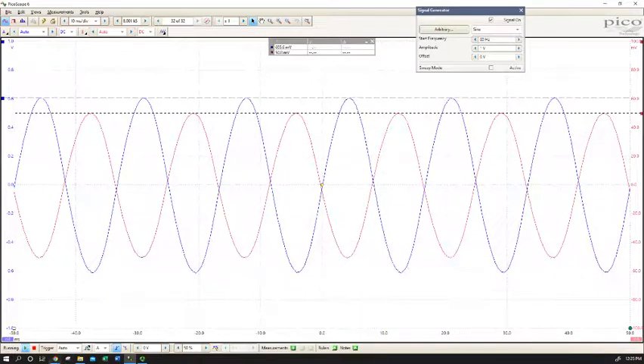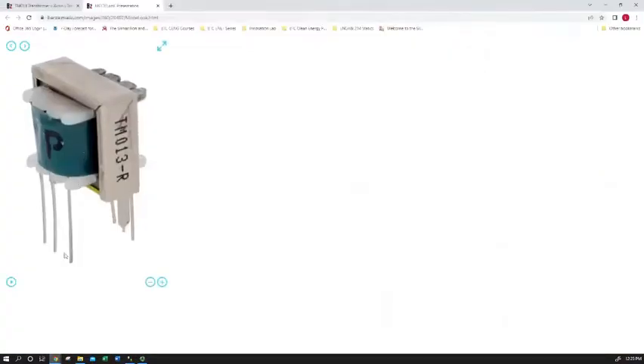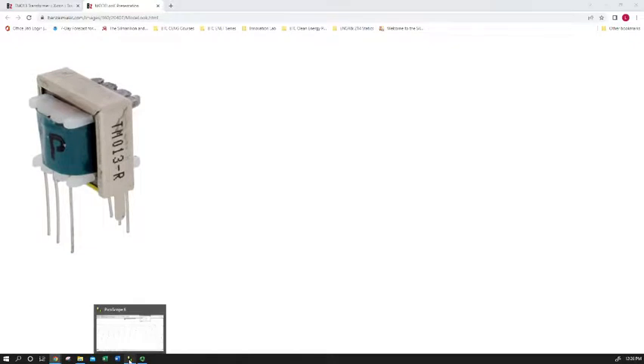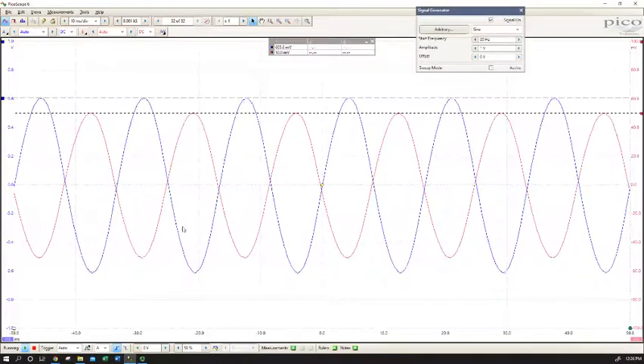Going back to the picture, I've deployed the positive side of my signal lead to this leg on the transformer, and I'm measuring with my scope leads to this leg and then this leg respectively. So I'm measuring the same physical end of the transformer as the de facto positive side, the side I'm measuring with my lead. That measurement location is giving me my primary and secondary waveforms out of phase, which tells me the polarity of the transformer.